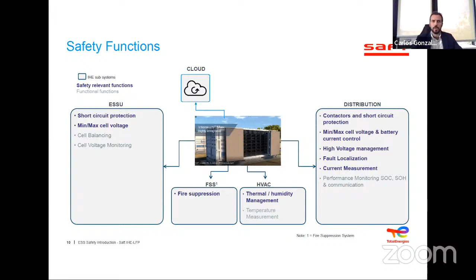Very importantly, if the system detects a fault like a voltage anomaly or high temperature, it will automatically activate the circuit breaker, and in a second step, if there is detection of fire, smoke, or CO, this will automatically trigger the gas suppression system.